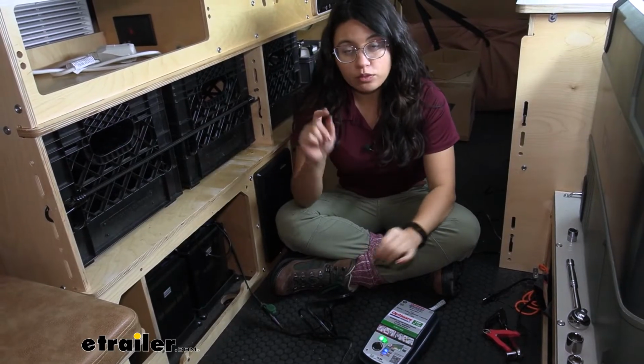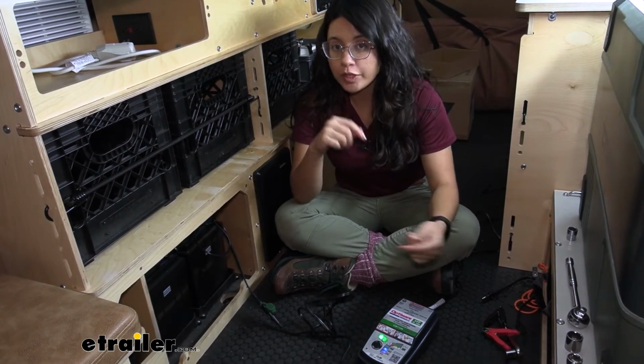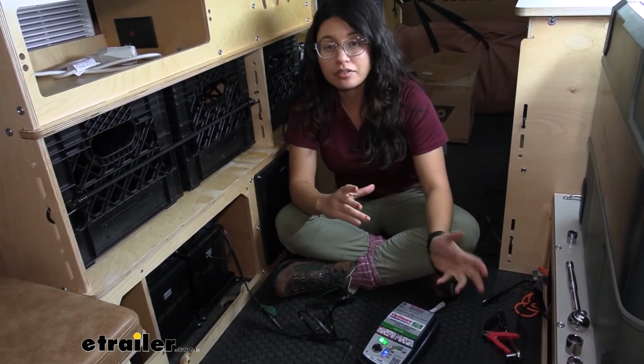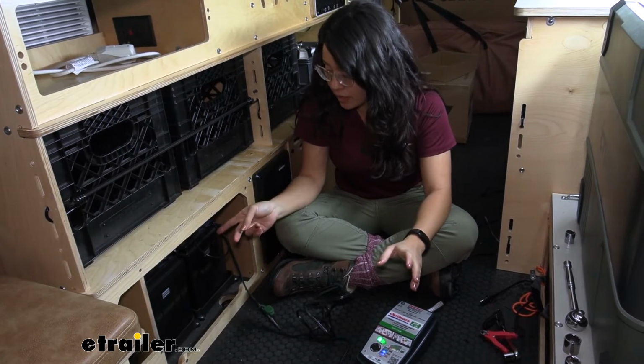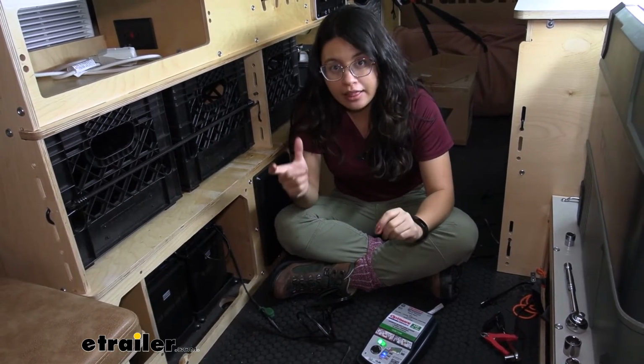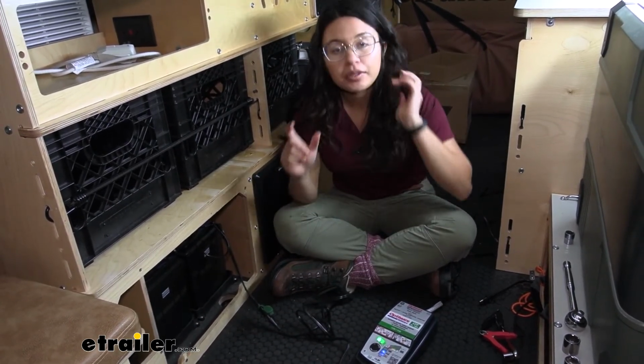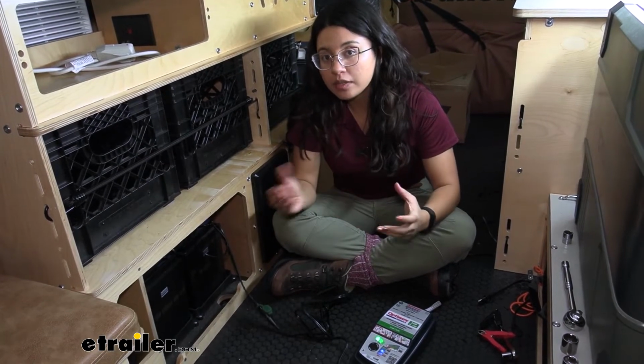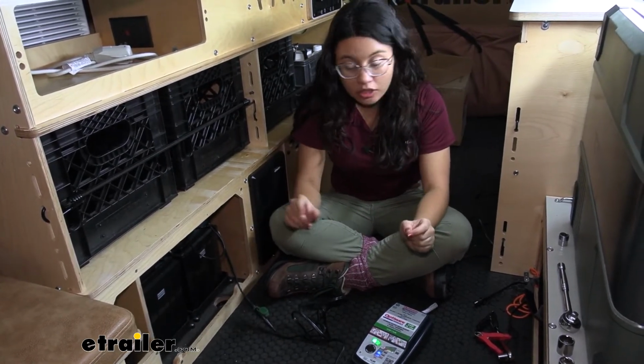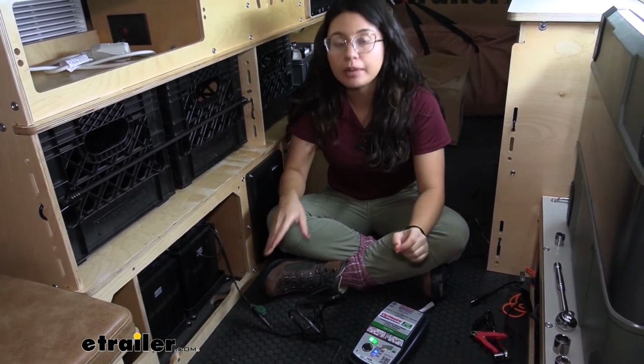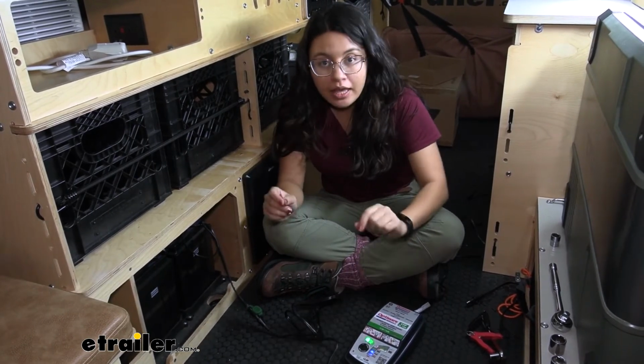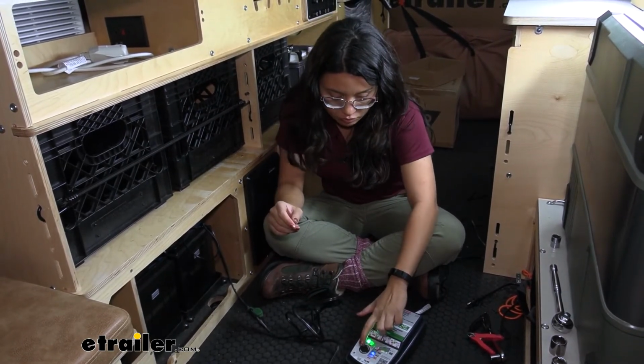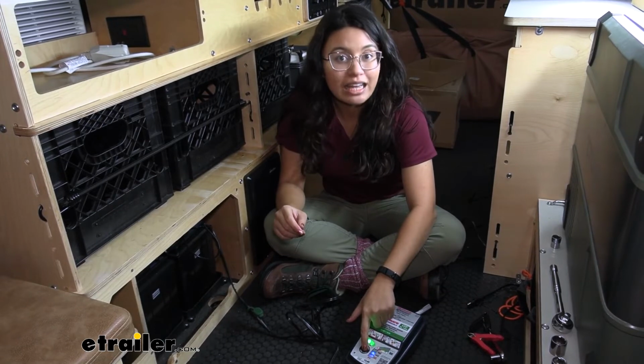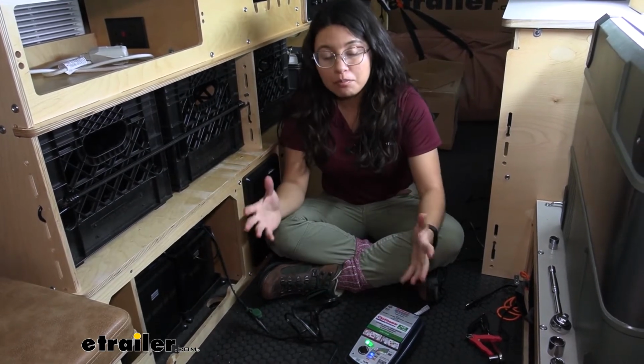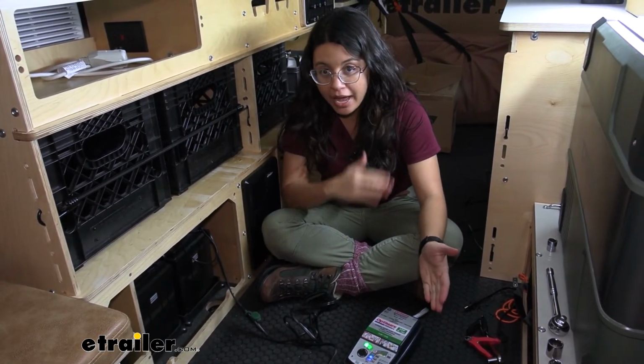Step one is when it connects to the battery, and this is when your protections come into place. Let's say you have reverse polarity and didn't set up your terminals correctly, that's when it sets off that error. Also, if your battery requires manual activation, maybe it has a special system, you'll have to manually tell it to start charging. That's the BMS reset for those types of batteries. But most normal batteries will go straight past step one.